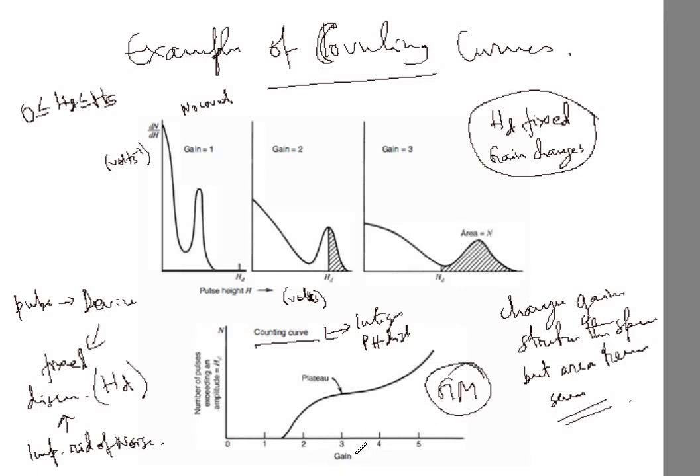But remember, that time instead of gain, you just used the detector bias voltage. Right. So as I was saying, why? Because the gain in a GM counter can be varied by changing the detector bias voltage or applied voltage. Okay.